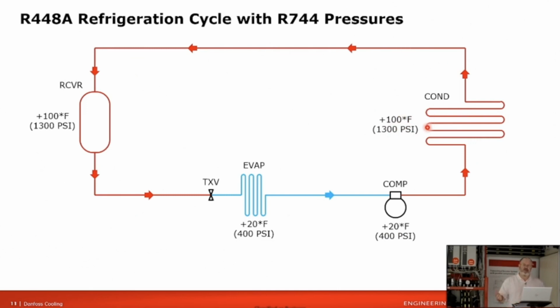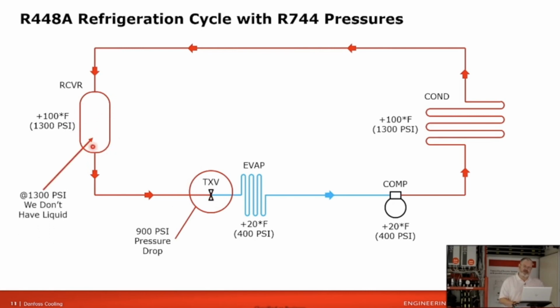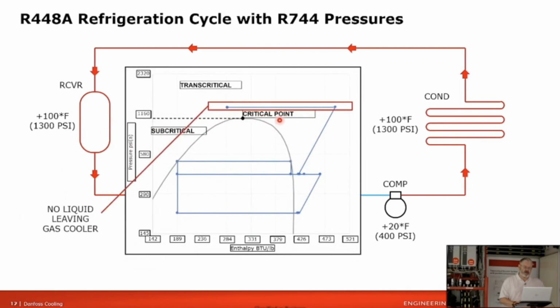So the first issue is going to be you burst all the piping because none of it's rated for 1,300 pounds. So that's a problem. And a couple of other things you'll notice is we have 900 pounds of pressure drop across the expansion valve. That won't work. I don't think selection softwares would even let you select that high. And then if you'll notice as well, we don't have liquid. Our liquid disappeared. And there's a reason for that. The reason our liquid went away is that at 100-degree ambient, remember, we're above the critical point. So when we get to this point, remember, we just charged a 448A system with 744. We didn't add components. We would basically get to here and nothing, we're above the dome. So it means we have no liquid. We're in the supercritical fluid region. Something has to get us from that point back down into the dome. And I'll give you a couple of moments to guess what that something might be.